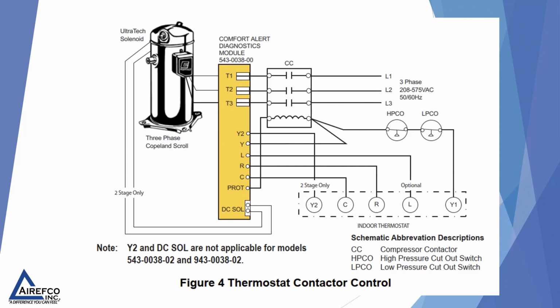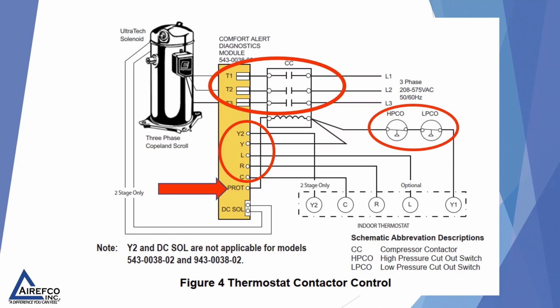The incoming power, L1, L2, and L3, is run through this device and monitors the voltage coming to the compressor at all times. It also has spade connections where you can run the thermostat connections through this device so that it will alert the end user if there's any problem on the thermostat. It also has a protection connection which runs through the high pressure and low pressure and any other safeties that may be on the system to immediately lock out the compressor if there's a problem. Because this device was designed by Emerson, it also has DC solenoid output for the Ultratech two-stage compressor.